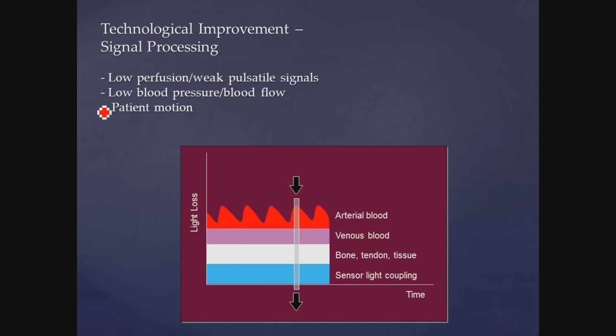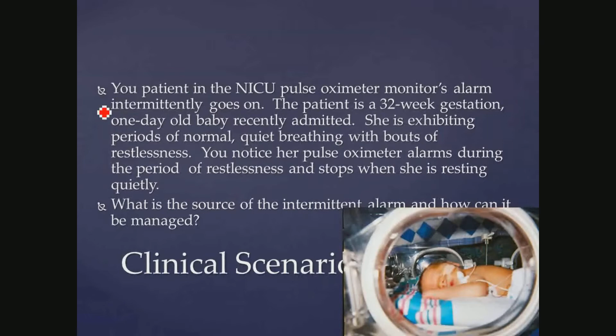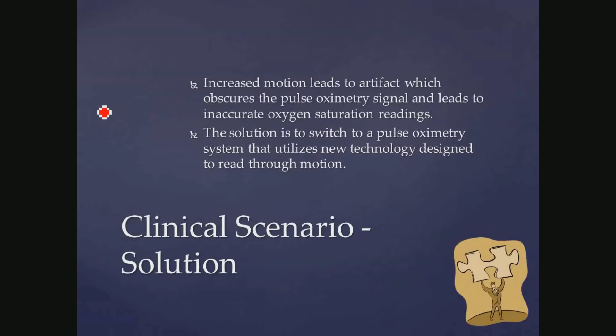32-week gestation baby, periods of quiet breathing with bouts of restlessness, pulse oximeter reading during this restlessness. When she's moving, you get a lot of alarms, and again, that's simply because of that inability to read through motion, and the increased motion obscures the signal. So using the newer technology makes sense. And like anything else, the algorithms have gotten better and better as time has gone on. So we're able to not only read through the motion, read through the artifact, but get a faster response in the process. And the calibration curves have improved with that also.